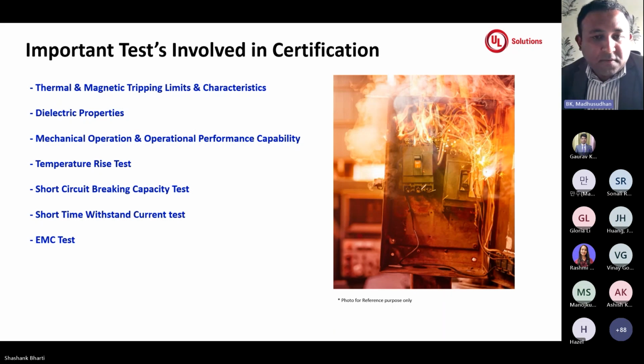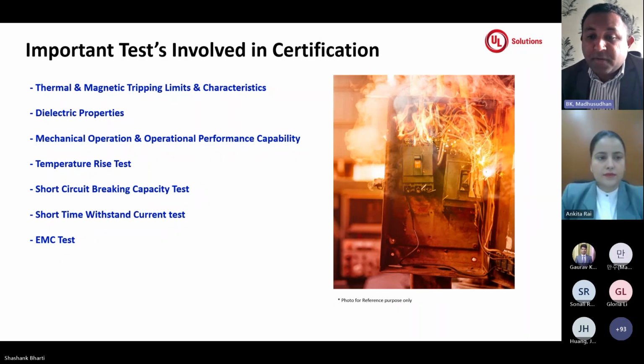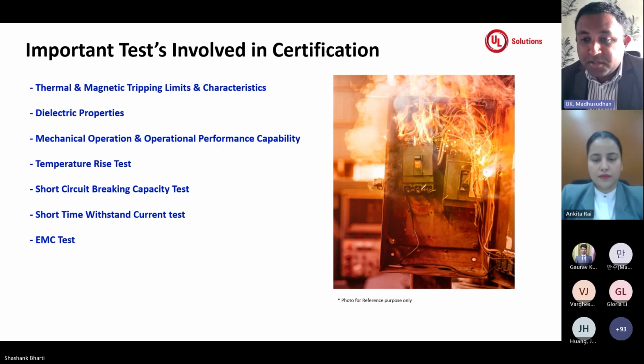Then coming to the test on operational performance capability, basically this is nothing but the endurance test. It covers both mechanical operations and electrical operations from the standard. So the breaker will be fed with the rated voltage and the rated current with the power factor specified in the standard, and the breaker has to undergo a number of operations continuously, with current and without current. At the end, once the number of operations specified in the standards are covered, the breaker should be in normal use without any deformation. The mechanism should be intact, and the contact should have complete continuity on the poles. All these will be measured at the end of the test, which is critical for this kind of product.